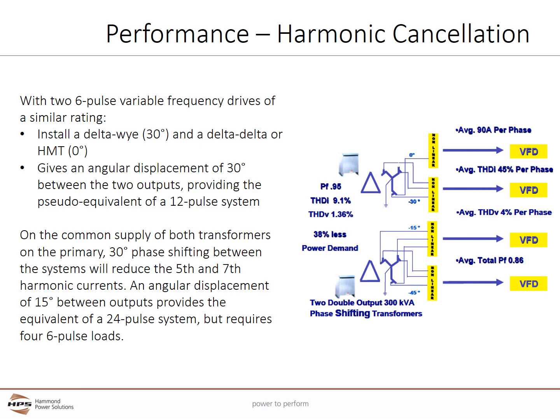Half of the total load is fed with traditional delta-Y DITs at 30 degrees phase shift. The other half of the load is fed with DITs using either a delta-delta or delta to zigzag neutral secondary. Usually the zigzag option is preferred. This creates a pseudo 12-pulse configuration. Due to varied loads and differing impedances and cable lengths, this configuration will have lower cancellation rates than a true 12-pulse DIT, but can still provide better cancellation than either a standalone DIT or reactor.